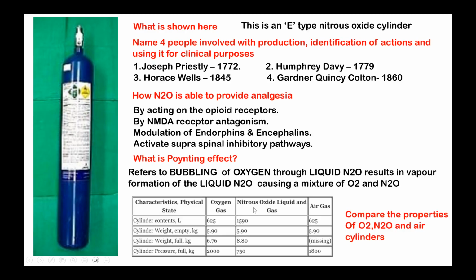So the cylinders, nitrous oxide is a gas at room temperature, and the cylinder weighs about 5.9. All E-type cylinders have the same weight, and when it is full, the weight will differ. Nitrous oxide will be heavier compared to oxygen, and cylinder pressure is very high in oxygen.